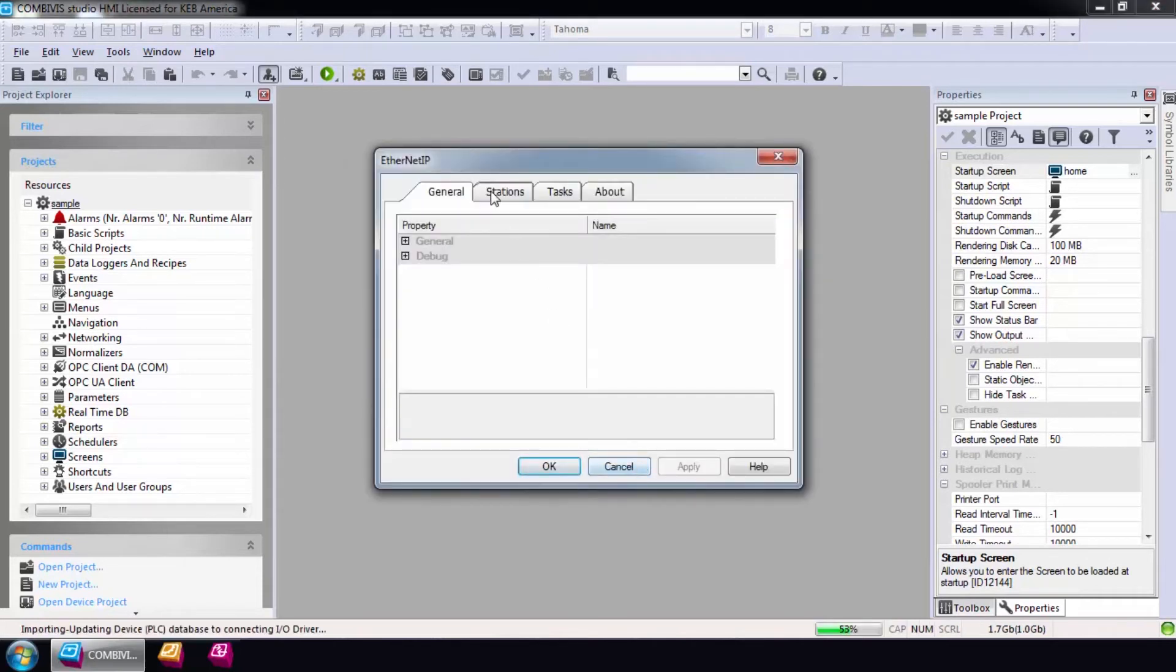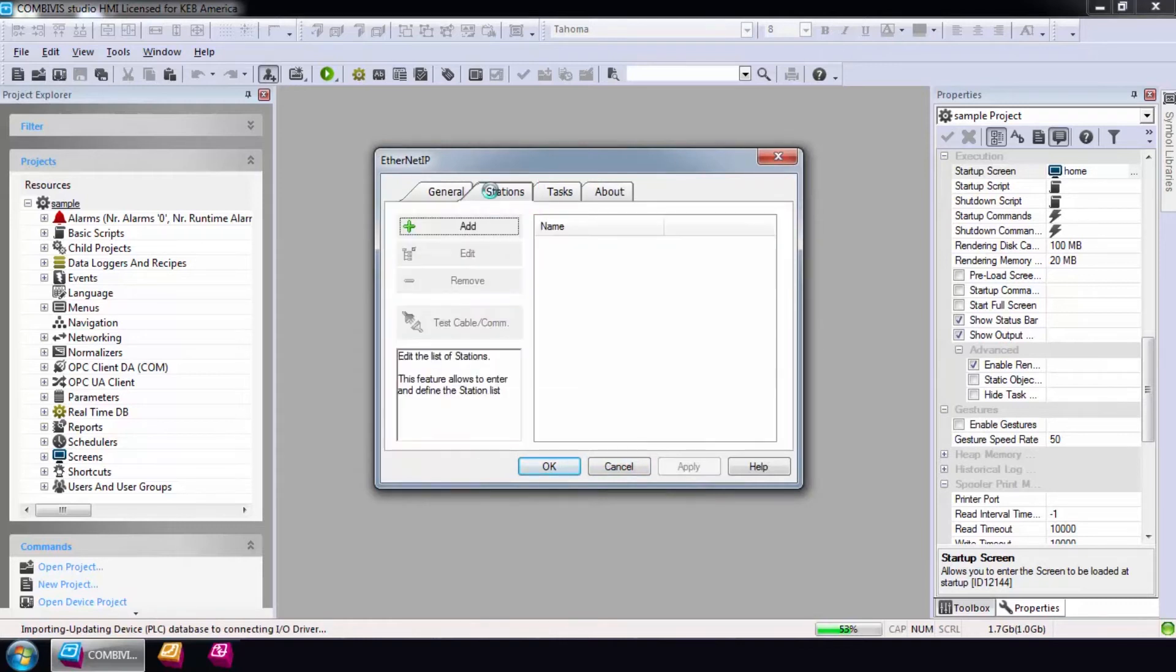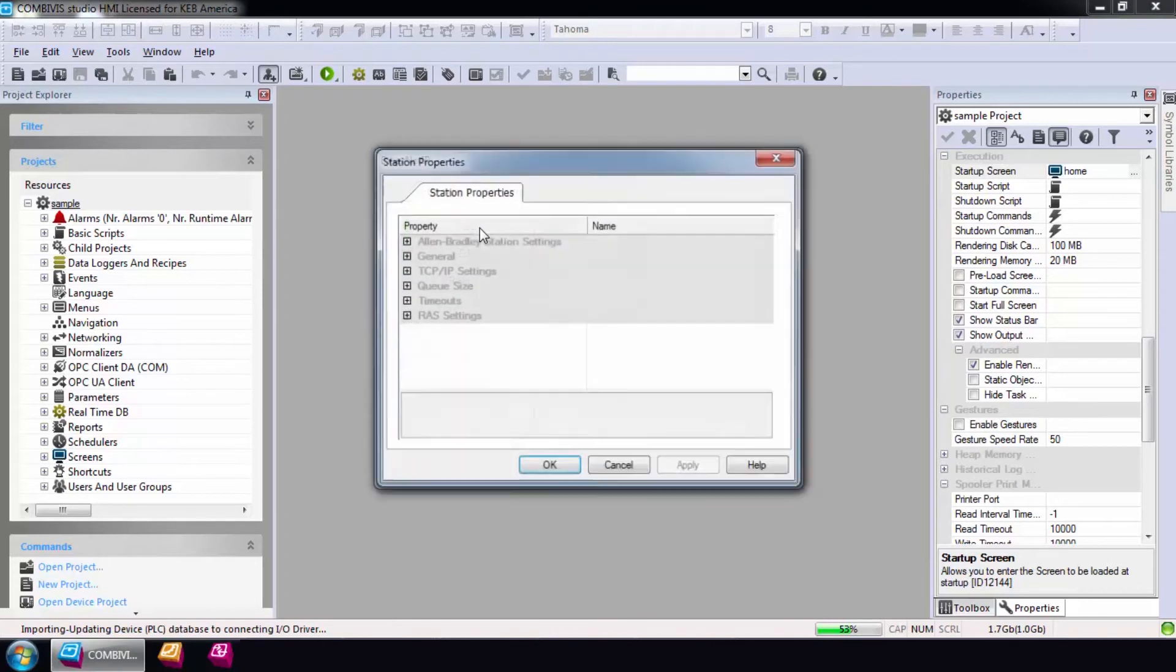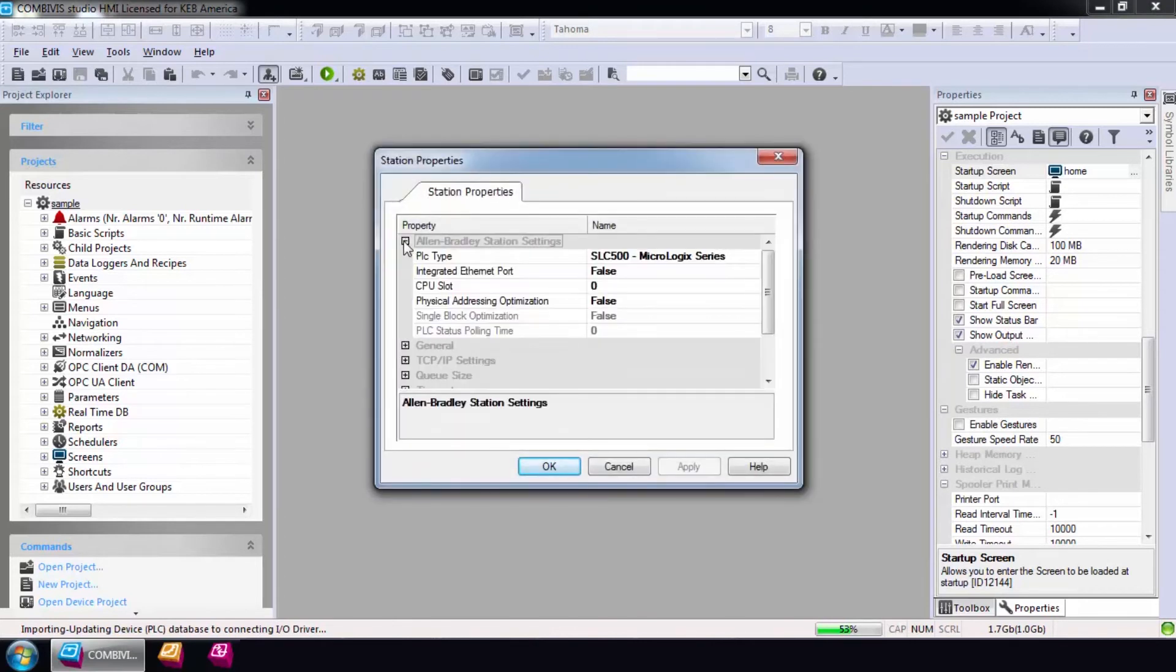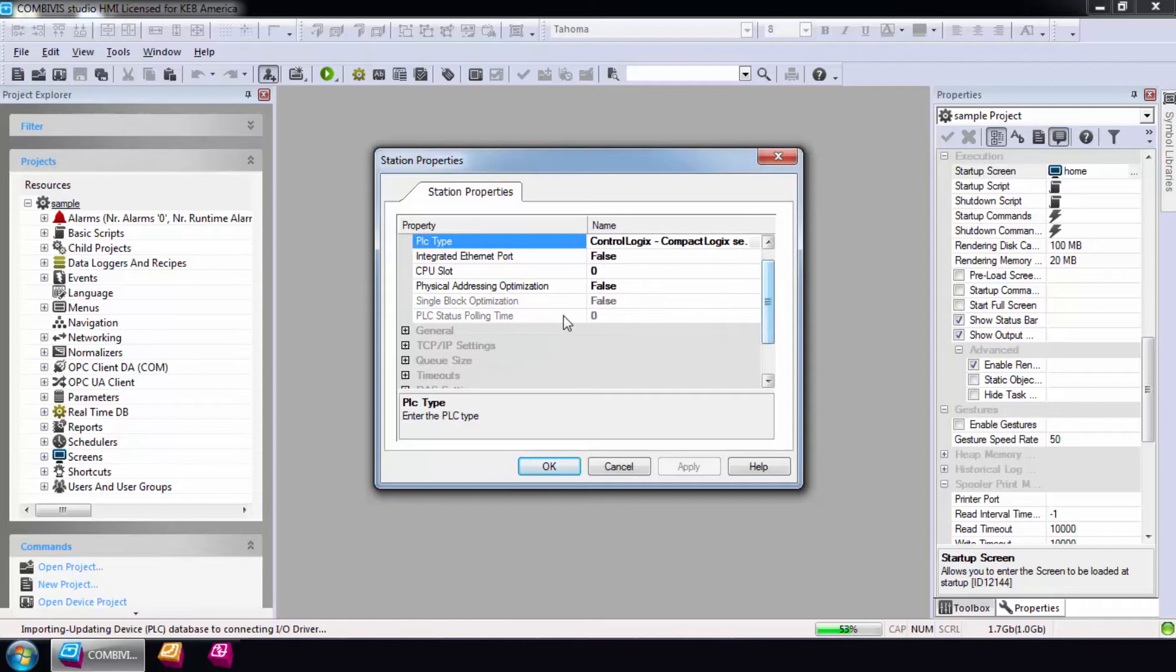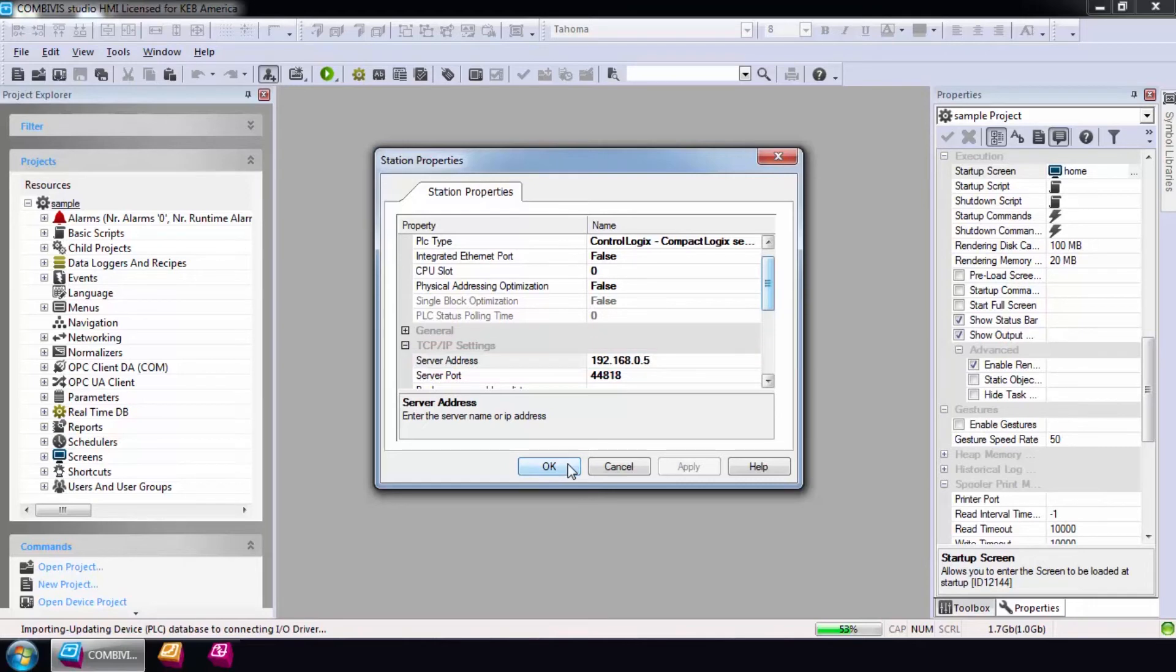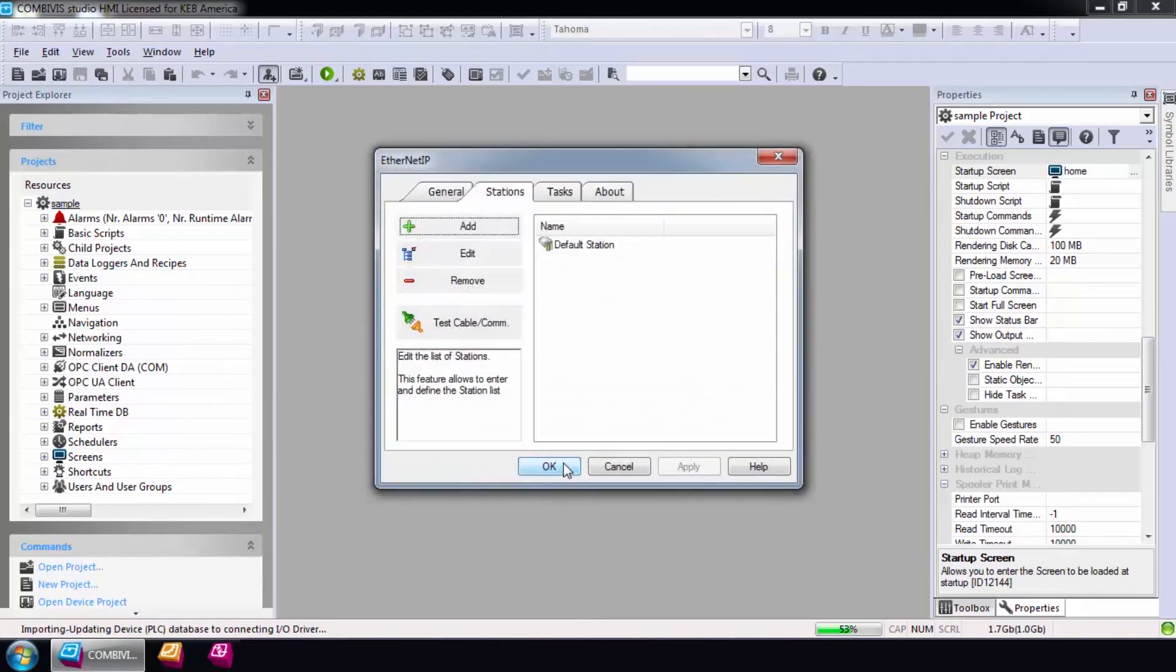The first pop-up you will see is the Ethernet IP configuration wizard. The only thing that needs to be configured here is a station with the correct IP address of the CompactLogix. Select Station and Add and modify the PLC type to CompactLogix. Then, scroll down and enter the IP address of the PLC. Select OK.